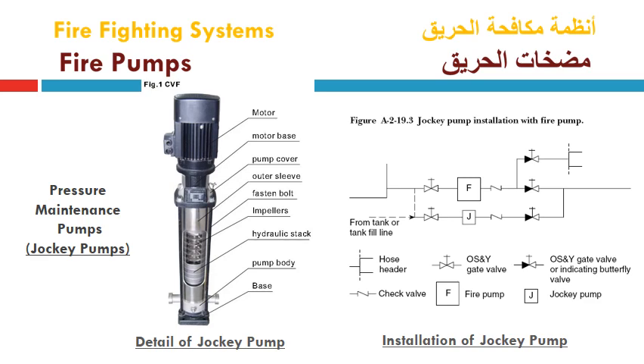This slide also continues the construction of the pressure maintenance pumps, the jockey pumps, showing the suction flange and discharge flange, and the shaft is located here, with the number of impellers affixed on it according to the required head per stage to get the total head of this pump, which may reach 300 feet or 350 or 400, as discussed in the previous slide. This is a nameplate, this is the motor of the pump, and this is the pump casing of stainless steel, and this is the base to be affixed here with bolts on the same base of the main fire pumps, or in between the electrical driven and diesel driven main fire pumps.